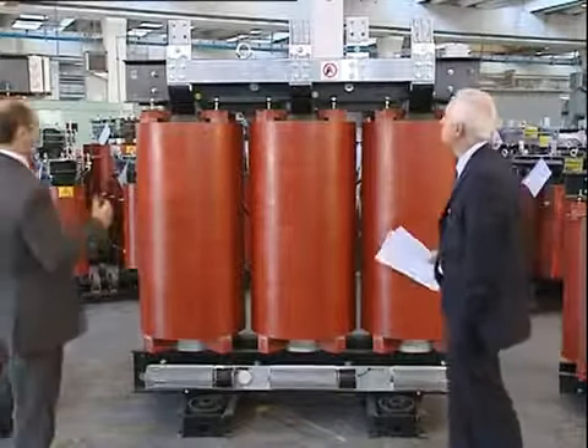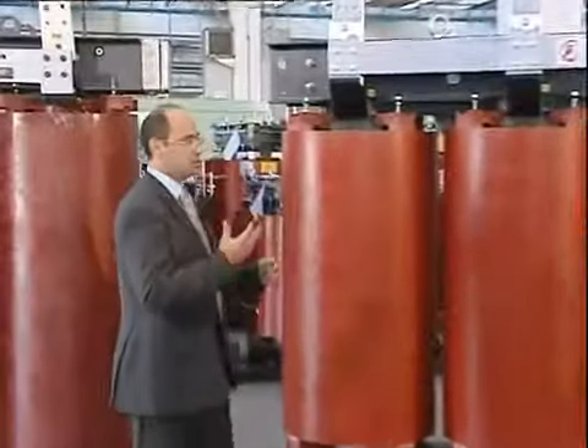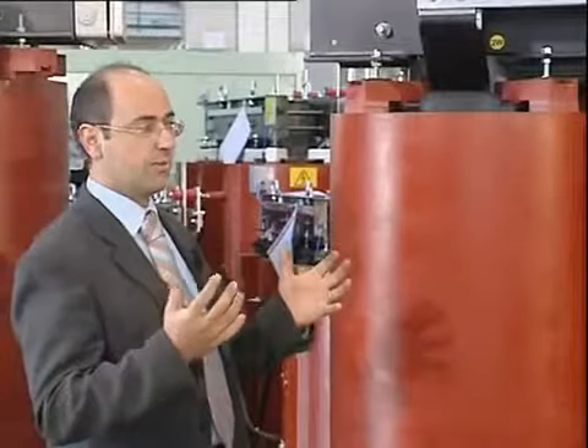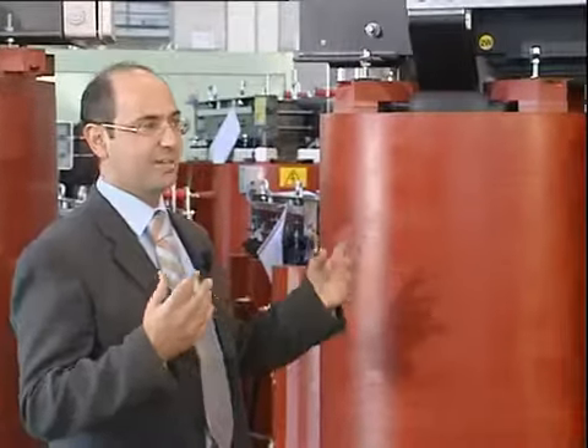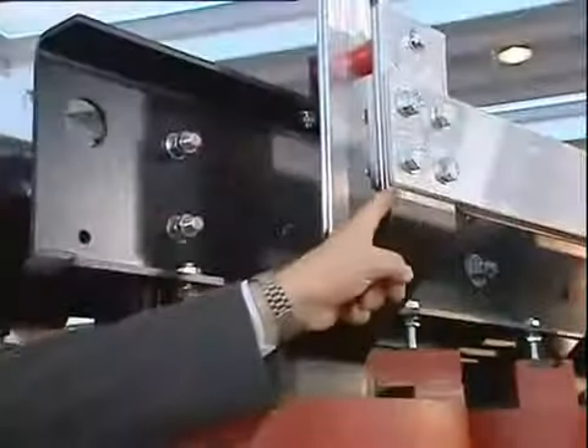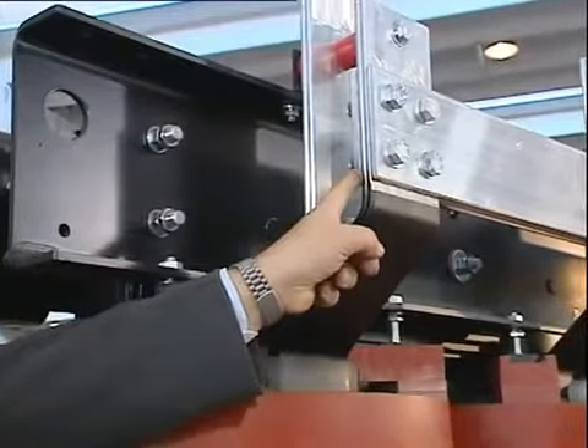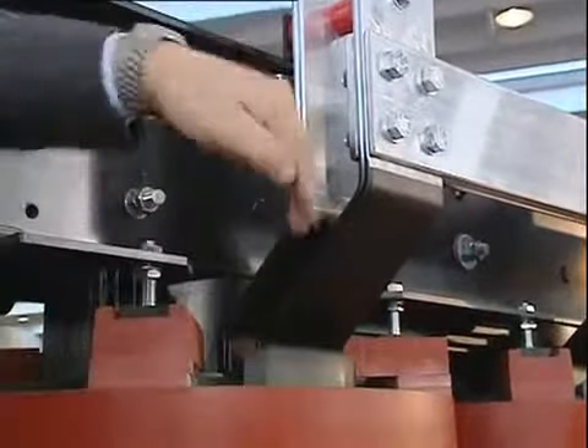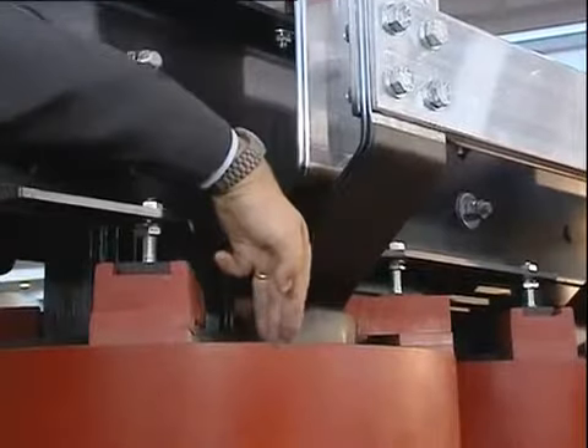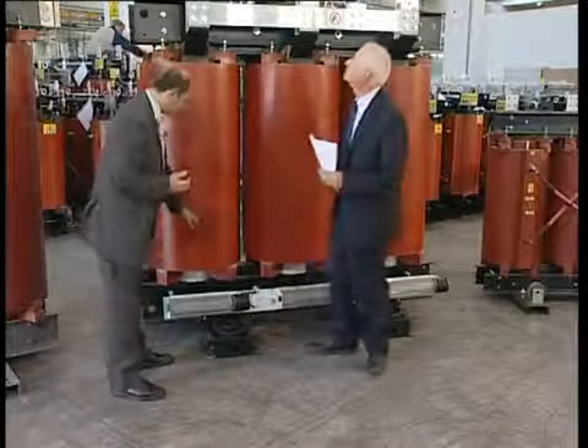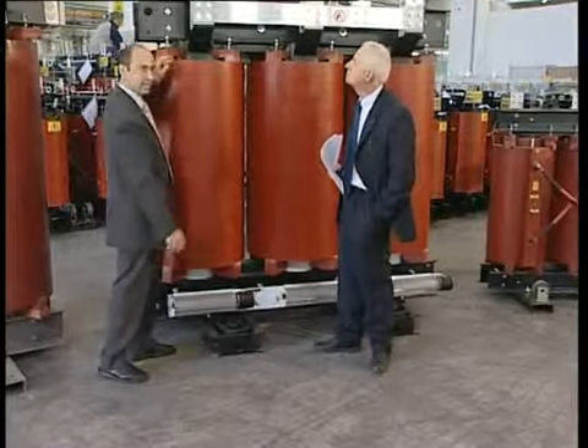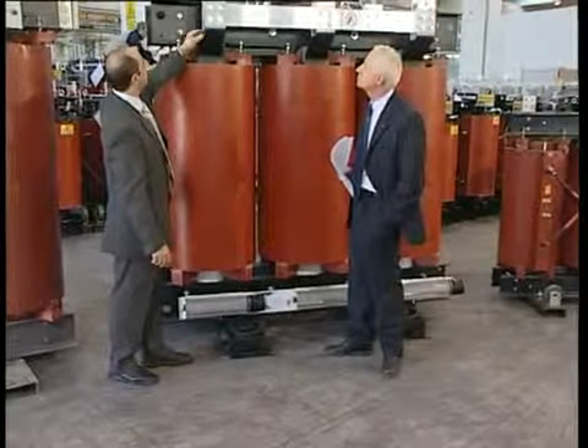Let's observe the most important aspect in a transformer capable of supplying approximately 3,600 amperes, i.e. the connections on the low voltage side. The outputs can be found on one single bar, starting from inside the winding. Does this double bar go all the way to the end? Yes, to the very end.